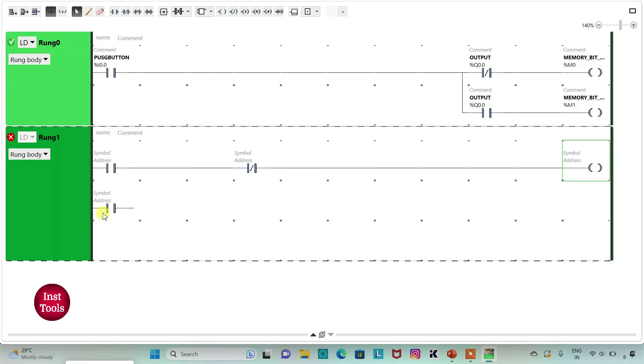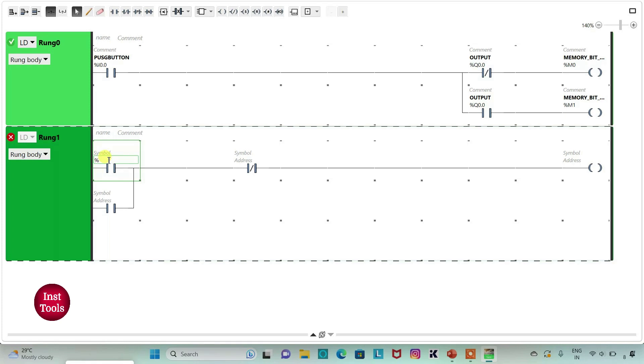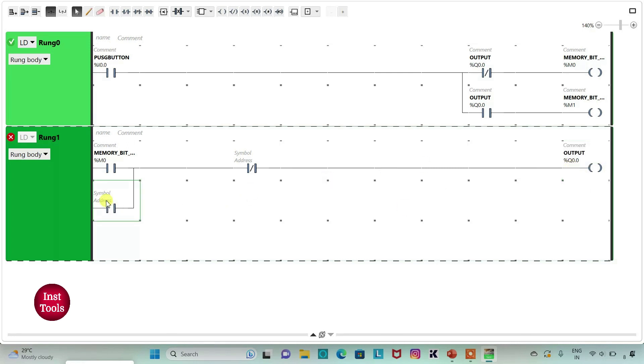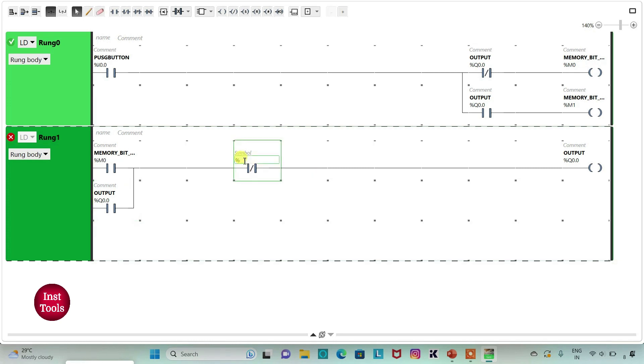I will join this normally open contact. I will click on this option and draw a line like this. And then I will assign address to this contact as M0, the memory bit which will be used to turn on the output. I will assign address to this as Q0.0. And then I will assign address to this normally closed contact, same as the memory bit which will be used to turn off the output, that is M1.